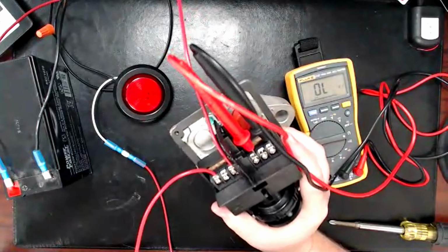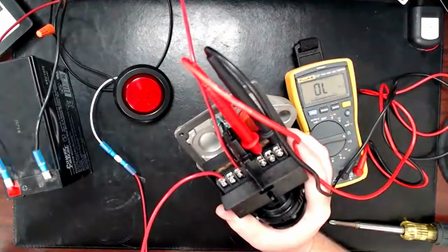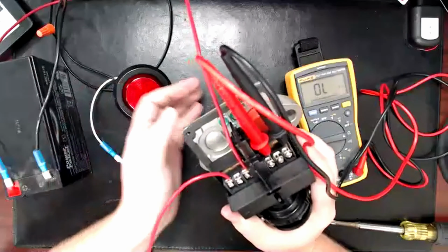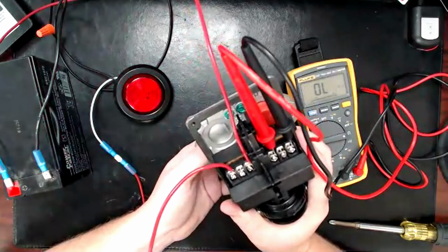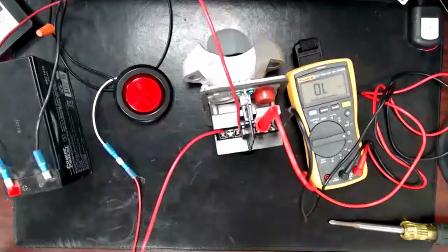In the case of a water flow bell, we're doing the exact opposite function. We normally want the water flow bell to be turned off. We don't want it ringing. And then whenever water does flow, it leaves its resting state and turns on. And so that bell is letting us know that there's water flowing somewhere in that building. And then whenever water stops flowing, the bell turns back off. This is the conventional way of hooking it up. This is the way it's been done for a long time.